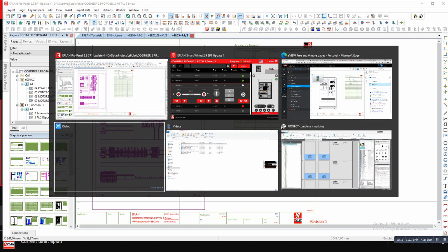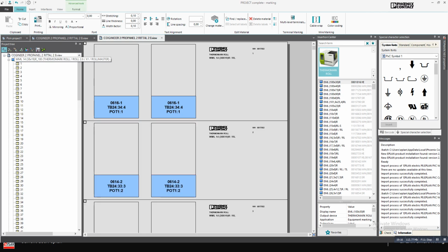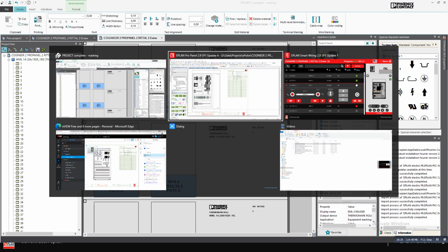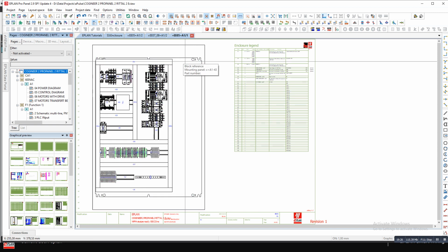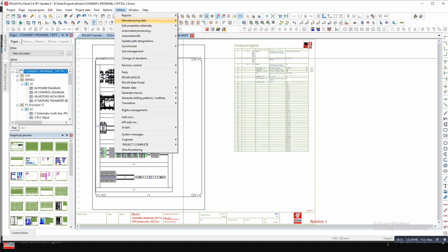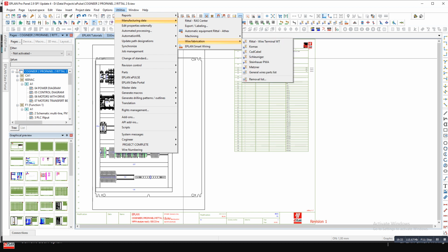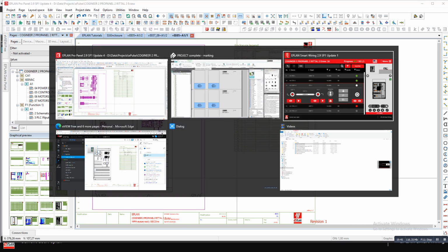All that, and the labels are here, you can see they just have to peel them off because I created all these labels automatically. Well, that can be reduced from an average of 180 seconds down to something like 30, 40 seconds if you start thinking about semi-automatic or automatic wire cutting, crimping, printing machines. Behind this, there's 1 minute roughly that we calculate to land the wires.